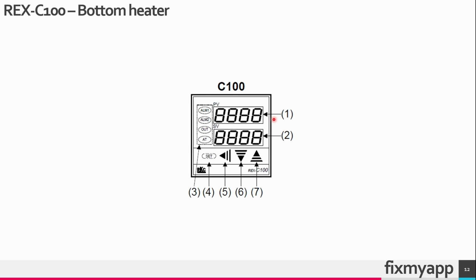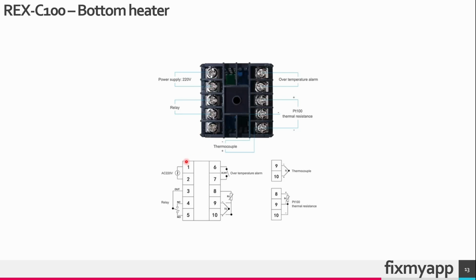This is the front side of this temperature controller, these are the buttons and this is the digital display. On the back side, on terminals 1 and 2 you will connect the main power supply. The solid state relay will be connected between terminals 3 and 4, and this solid state relay will drive the bottom heaters. It will drive the 4 ceramic heating plates. The thermocouple that will measure the temperature for the bottom heater will be connected to terminals 9 and 10. The negative lead will be connected to terminal 9 and the positive lead will be connected to terminal 10.